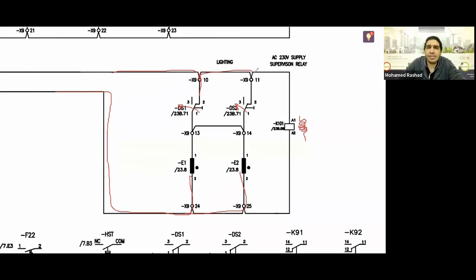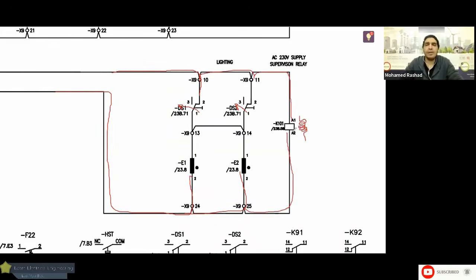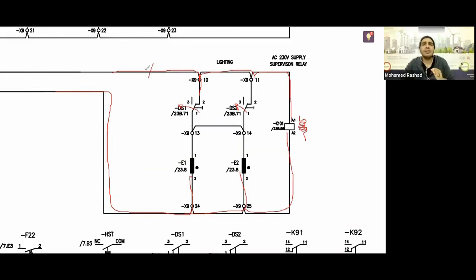The AC supply is connected here from the top and from the bottom, meaning it's energized all the time. If there's a break anywhere in the circuit, whether in the line or neutral direction, this coil will immediately drop off. Using its auxiliary contacts, normally open and normally closed, I can send an alarm to the annunciator, to the DCS, to the SCADA, telling you there's a problem in the AC circuit. This is called AC supervision.